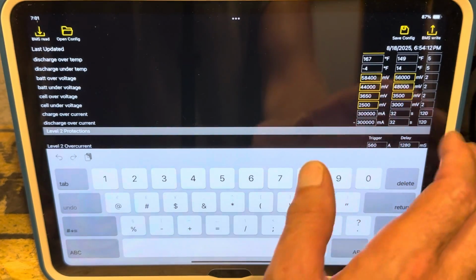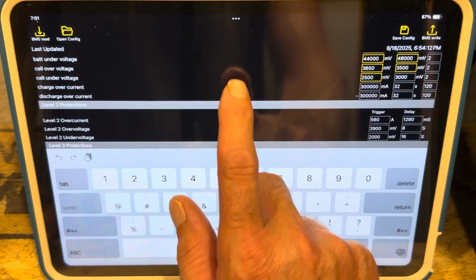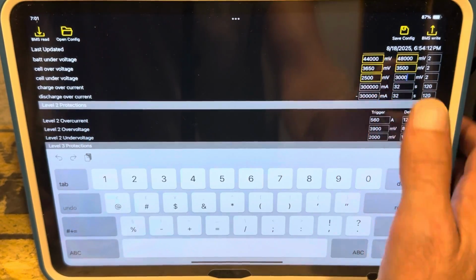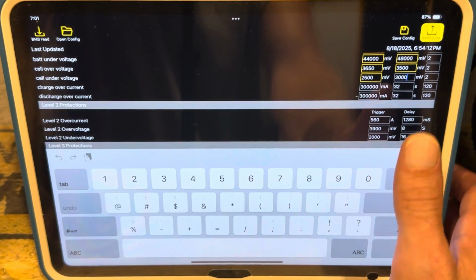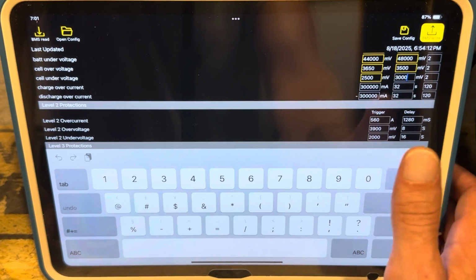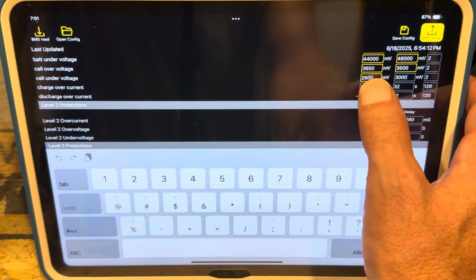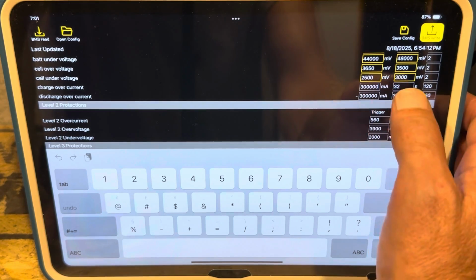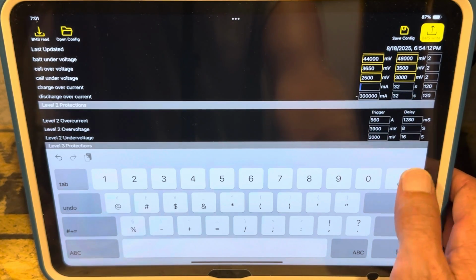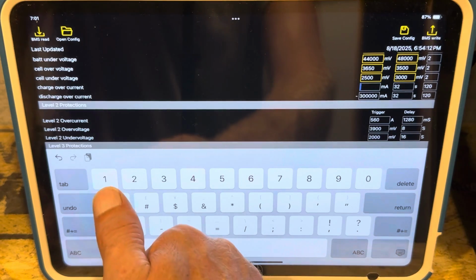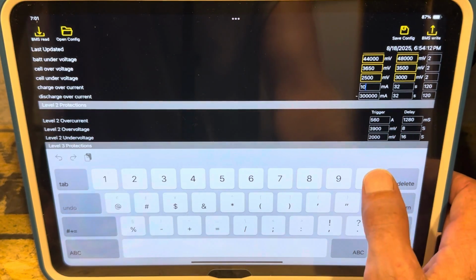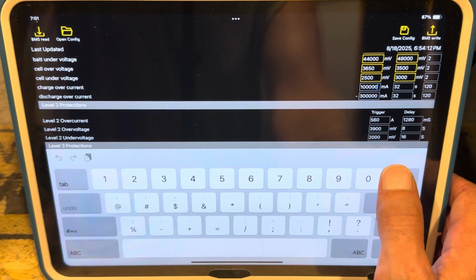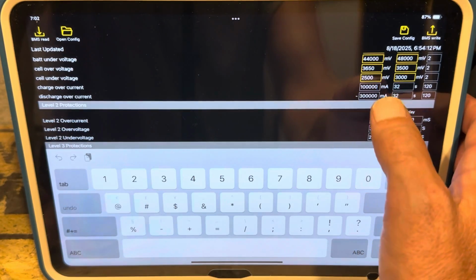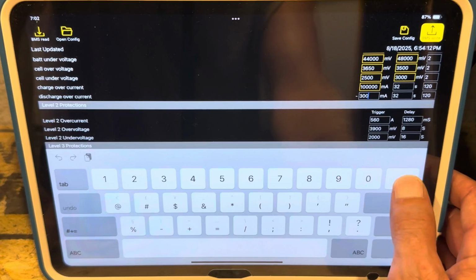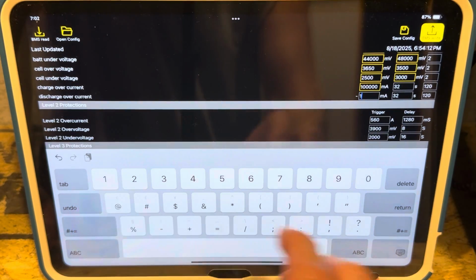Then we'll go down to the charge over current and discharge over current. 300 amps is good for a golf cart - most of them don't need that, but it gives you plenty of room. I'm going to change that to 100 amps. Remember, this is in milliamps, so remember to divide out. This is 100 amps, so I'll do 100,000 milliamps on the charge, and the discharge I'll do 100,000 as well. That'll be equivalent - 100 amps.